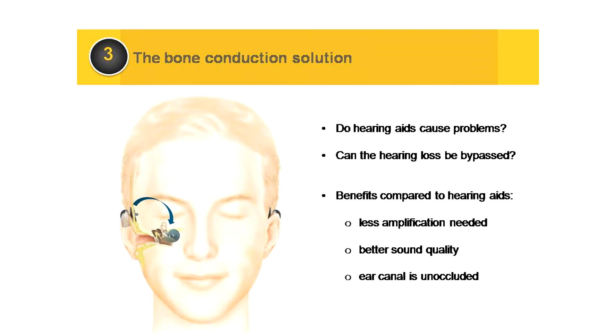Unlike hearing aids, bone-anchored systems bypass the problem area in hearing and go direct to the cochlea, which means they need less amplification to do the same job for the patient, which leads to good things like less feedback loops and annoying noises and whistles. It leads to a better sound quality because it's going direct to the cochlea rather than having to force its way through the blocked problem area. And it leaves the ear canal unoccluded, which is really important for patients with discharging ears, and often leads either to a cessation of the discharge or much reduced discharge in the future.